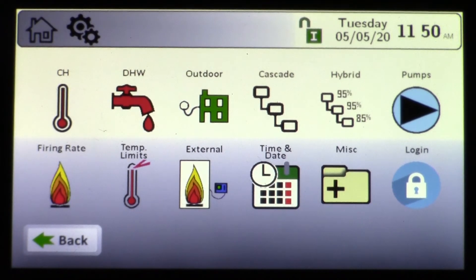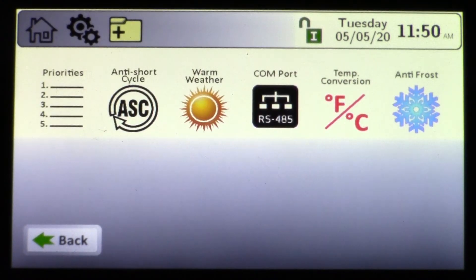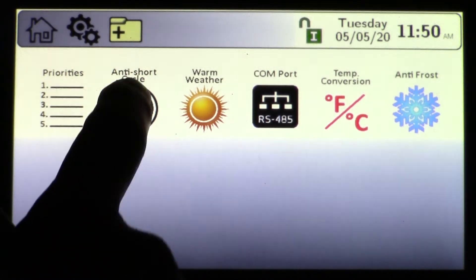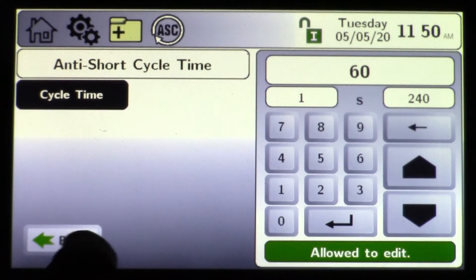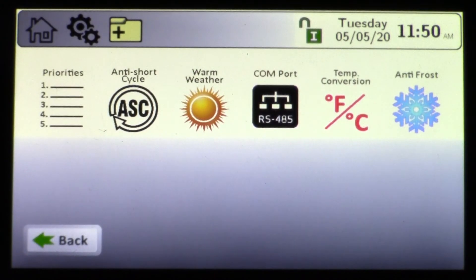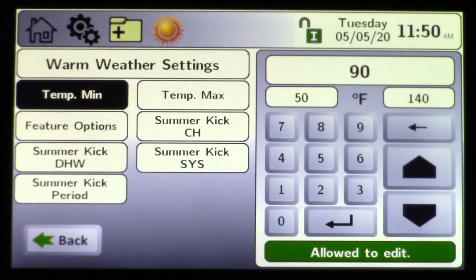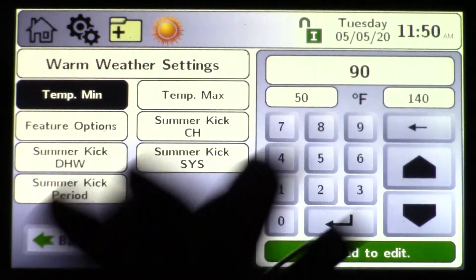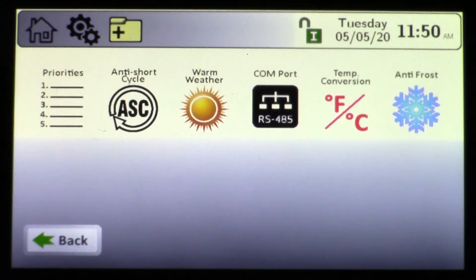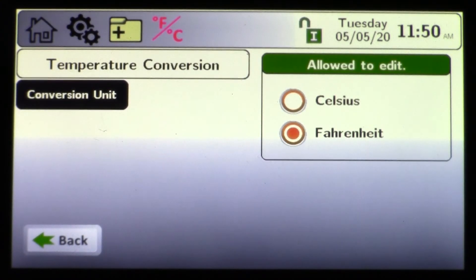Date and time we've already covered under quick start. Under miscellaneous, anti-short cycle and warm weather shutdown are also here. Anti-short cycle time — 60 seconds is the default. For warm weather shutdown, you can choose a value — hypothetically 72 degrees. If a demand comes for a heat zone while it's above that set point, the heating system will not operate until you're below that warm weather shutdown temperature.